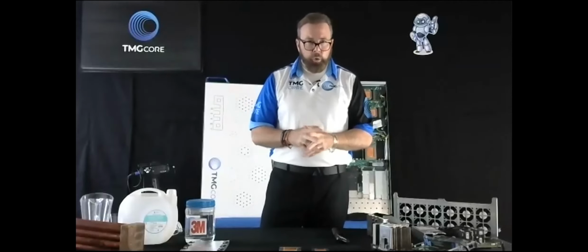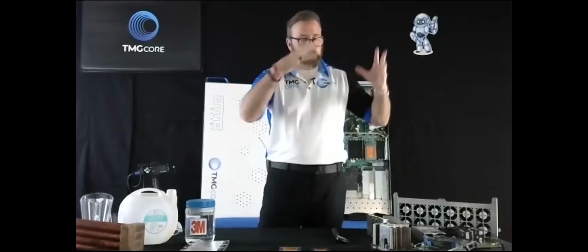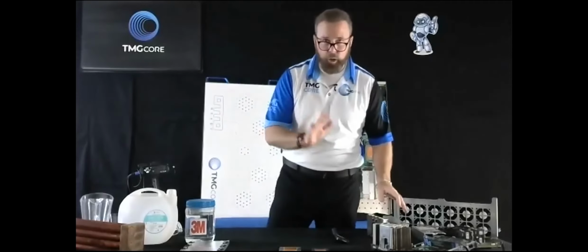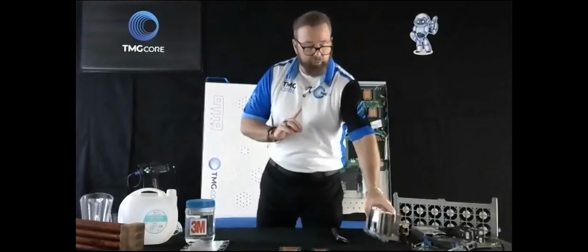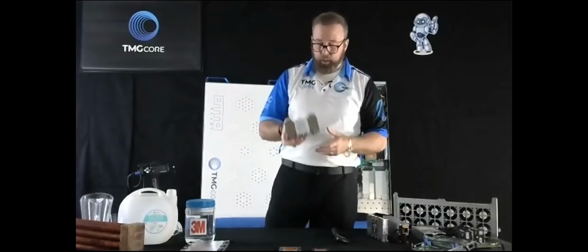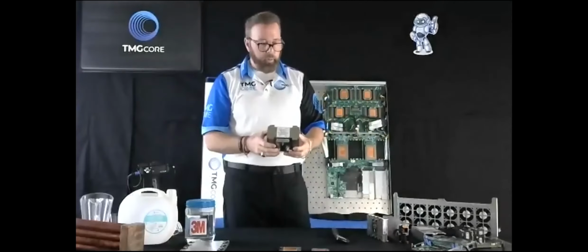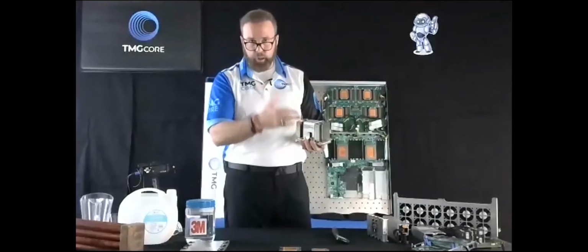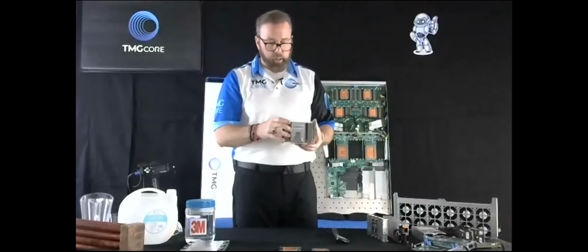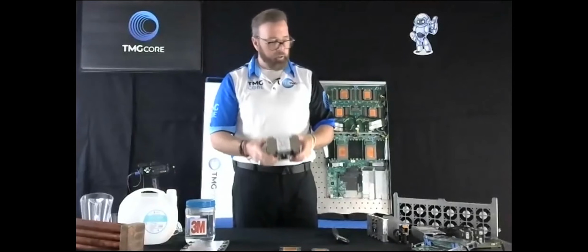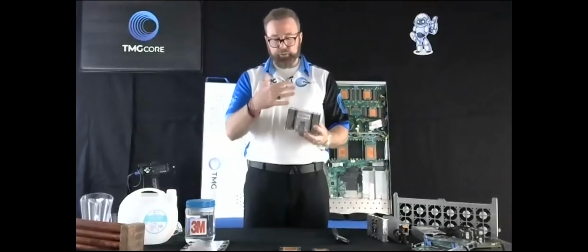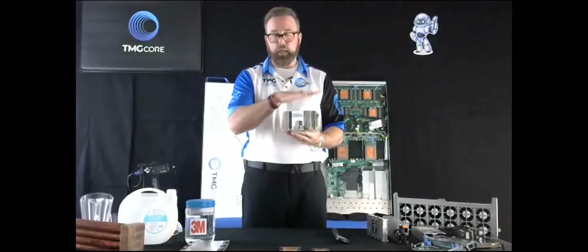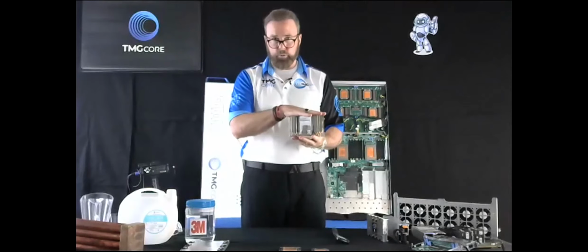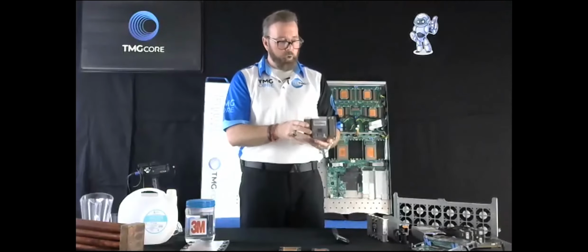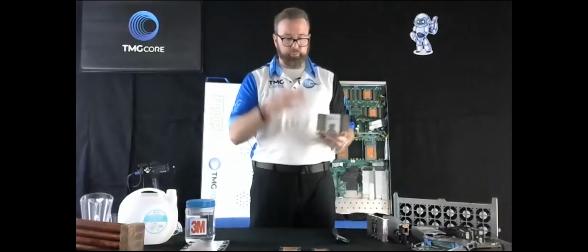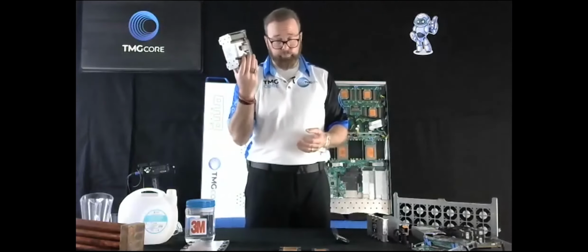In the case of air cooling, you have chillers and filtration systems, because one thing you don't want is dust building up. You need to filter the air, which keeps pressure drop across the filter. If dust gets on the chips, it basically bakes on there, causing a degradation in thermal transfer. Then you have to ramp up the fans, cool the air more, or the system fails.